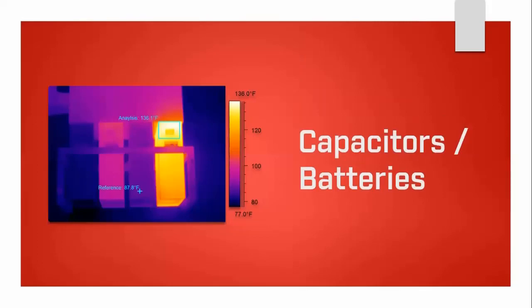Capacitors and batteries are generally passive devices with not much heating at all. This case clearly shows one capacitor heated much more than the other, which only shows a slight warming. Examine this circuit and determine if the discharge resistors are engaged or if the capacitor is damaged — secondary testing with other methods is warranted in this case.